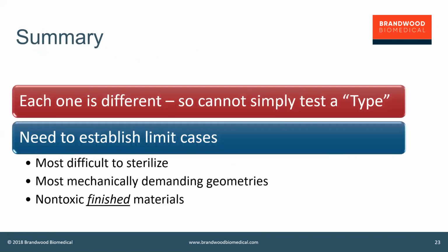So in summary, the challenge with 3D printed custom devices is that each one is different. You cannot simply test a type. You don't have a mass-produced device where everyone is the same, where you can test that and validate and verify the performance by testing a type, essentially. So what we need to do is effectively establish limit cases.